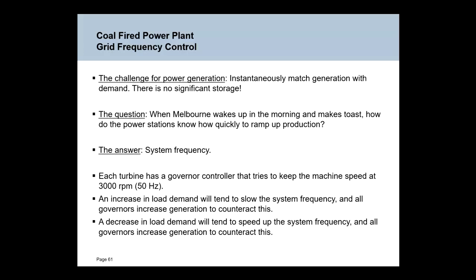The frequency starts to drop. All of those power stations see the frequency drop. They have control systems that are monitoring the frequency, and they recognize they have to put more megawatts in the system in order to bring the frequency back to 50 hertz. So they then start to generate more megawatts. They burn more coal, more gas to generate more megawatts, and the frequency comes back up again.